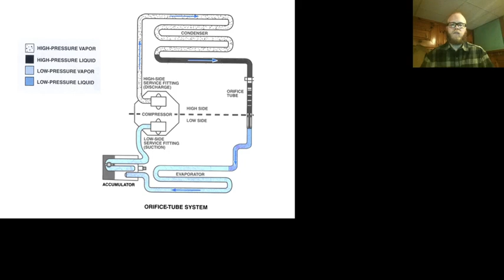Safety precautions when working with refrigerant. Refrigerant evaporates at low temperatures, right? At ambient pressure, which would be whatever we're standing in the shop, it's going to evaporate at negative 24-ish degrees, and that's going to be more than enough to, if you open up a line by accident or open a bottle and don't have it connected to anything, it's just going to immediately vaporize and fill the area that you're in.